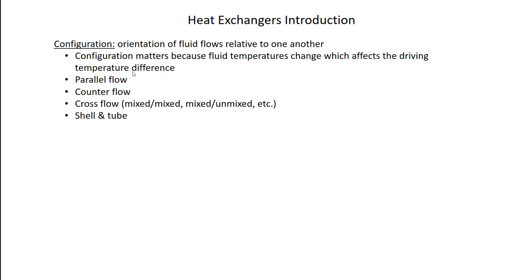Direct transfer heat exchangers are classified in different ways based on their configuration. What makes a heat exchanger complicated to analyze is that the hot fluid comes in at a high temperature and the cold fluid at a cold temperature, and they don't stay at those temperatures — the hot fluid temperature drops and the cold fluid temperature rises. The manner that this temperature difference evolves depends on the orientation of those flows relative to one another, which is captured in what we call the configuration. So we have parallel flow, counter flow, and cross flow.